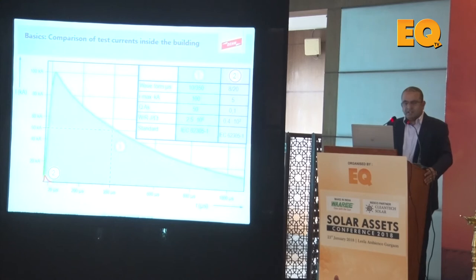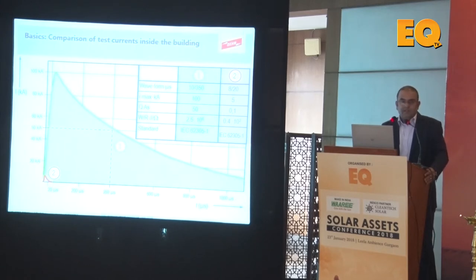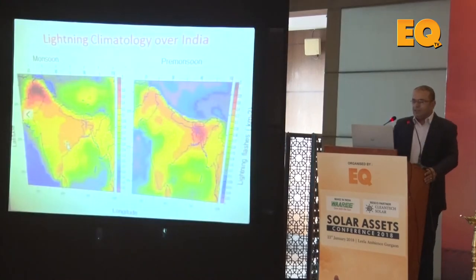There are also surges on the grid, and those surges can travel through the inverter to the panels, and sometimes can damage even the inverter itself. Lightning or surges can damage solar panels, inverters, or combiner boxes like the BOS system. So your BOS system requires its own protection—this is called lightning protection.